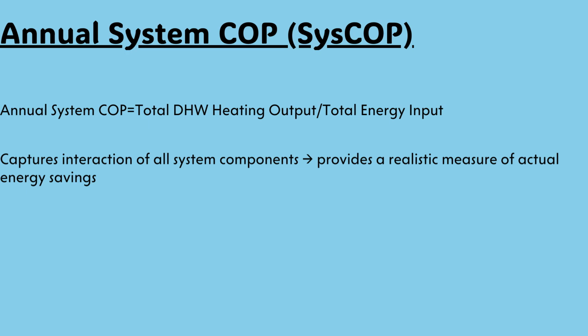When designing a domestic hot water system for your building, consider your SysCOP. SysCOP accounts for the entire system: the heat pumps, the storage, the temperature maintenance, and the way everything works together. It's calculated by dividing the annual energy delivered as hot water by the annual energy consumed. SysCOP gives owners, designers, and policymakers a much clearer picture of real-world performance. That's why programs like the Advanced Water Heating Specification and the California Energy Commission's compliance approaches now evaluate systems based on SysCOP rather than just individual equipment ratings.